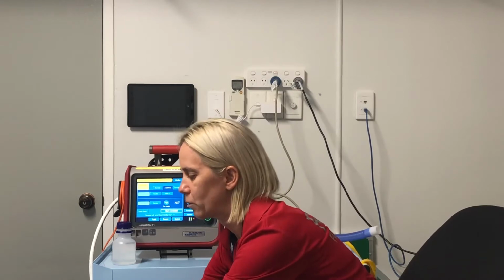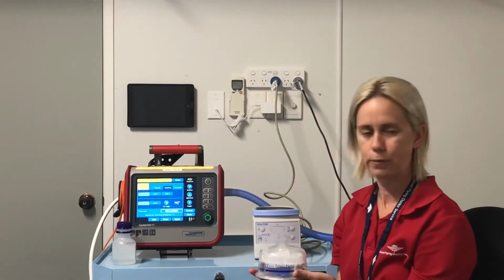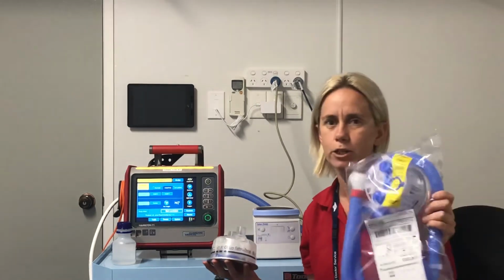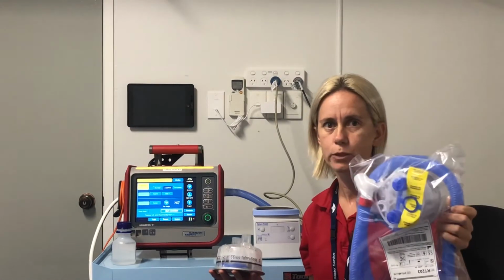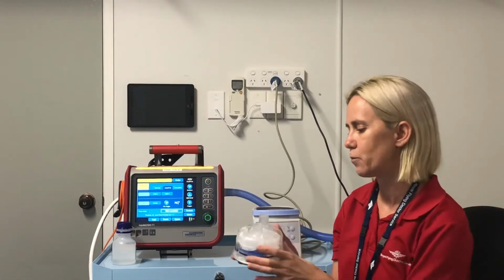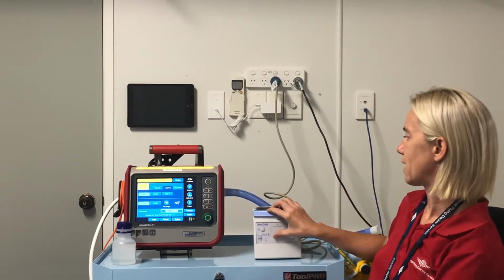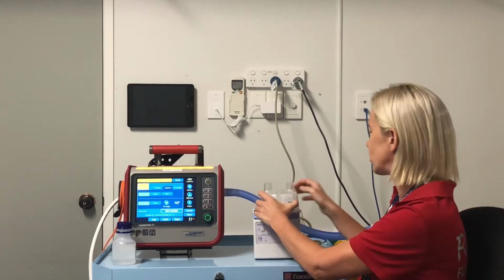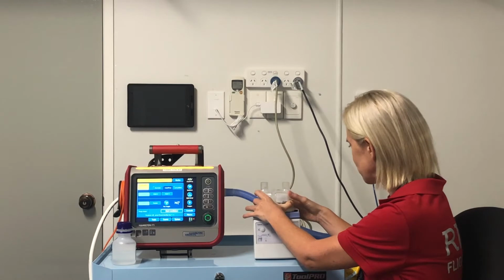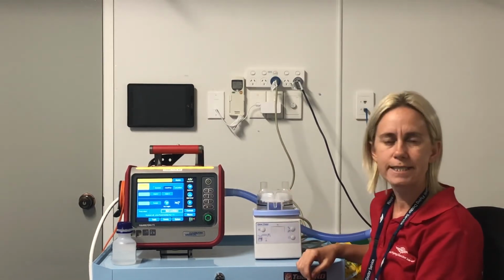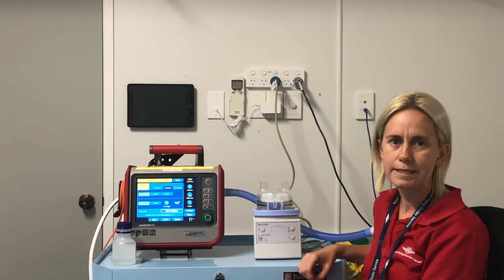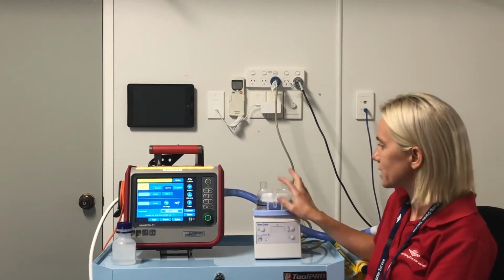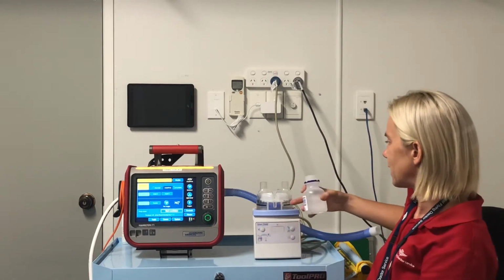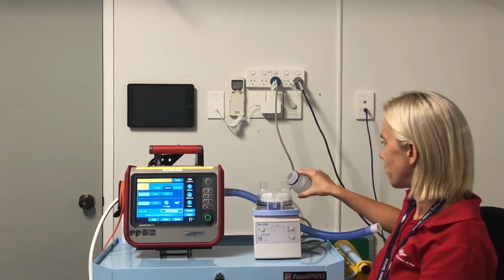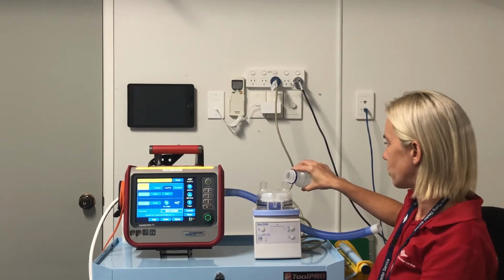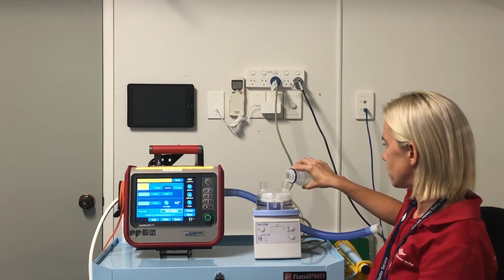So now that we're ready to set it up, we need the pack, which we would open depending on if you got the pediatric patient or the adult patient. You decide which one you need, and so today we're just going to use this demonstration one. So to pop it into the humidification chamber, you press the blue button down and it generally just slides on. Perfect. Once that slides on, what we'll do is we'll add some sterile water into the chamber. So you don't want to overfill it. It has got the blue mark there, so generally no more than that. So you just pour a bit of sterile water in there, and this is what humidifies the oxygen. I'll just pour a little bit in.